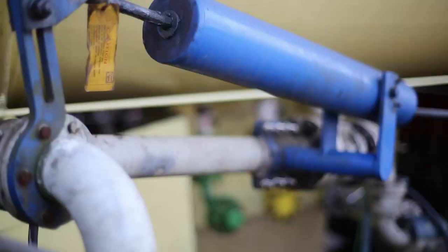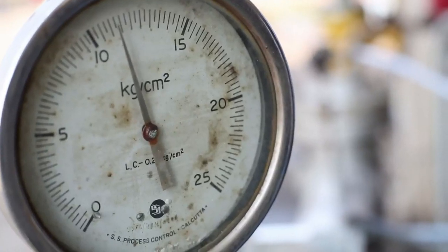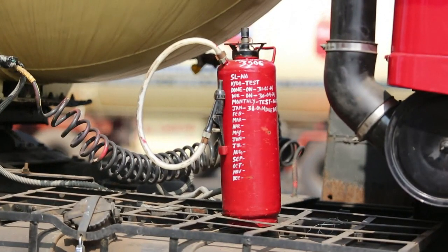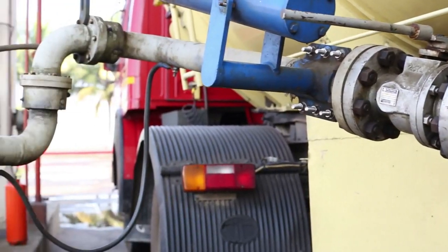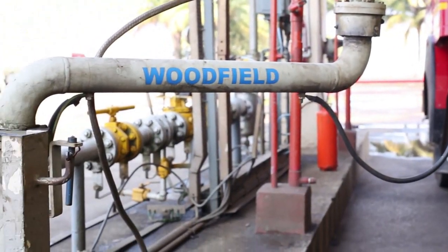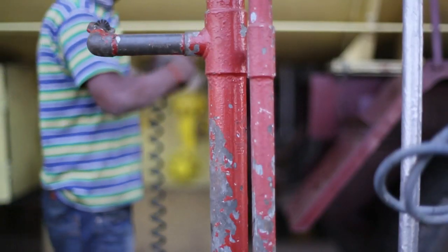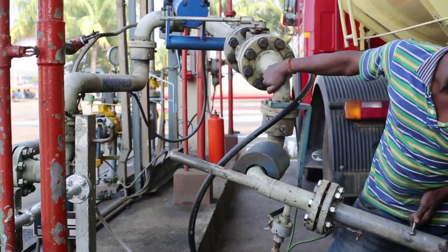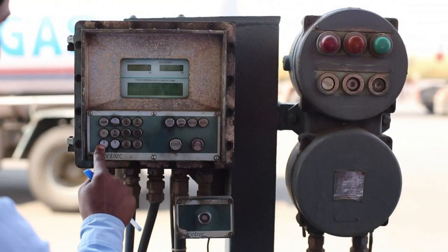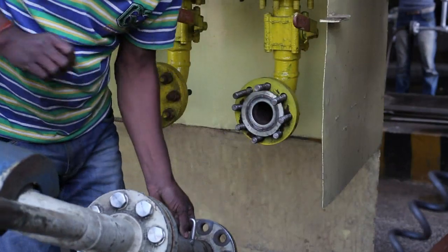Prior to loading, all valves are checked to ensure they are in operational condition and their fittings are of 300 class rating. Each truck is equipped with an approved and fit fire extinguisher. While the truck is parked in the loading bay, the isolation switch should be in the off position to isolate the battery and ensure no current flows through the vehicle during loading. An earthing strip is safely secured to ground the vehicle and avoid any spark due to static electricity generated during loading. Drivers must be positioned at the loading arm while loading takes place, and only after the loading arm has been disconnected can the vehicle be driven away.